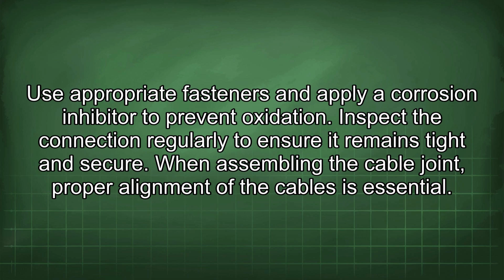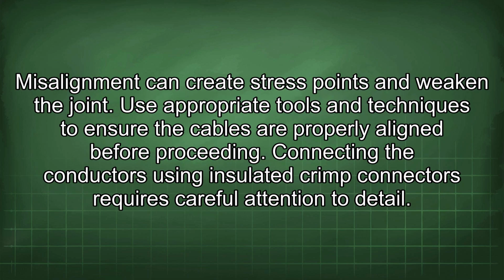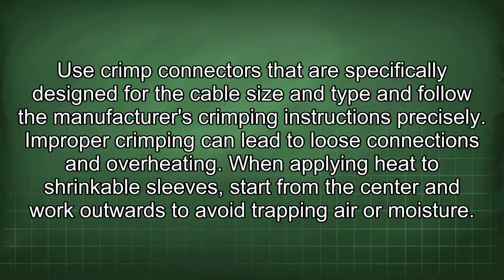When assembling the cable joint, proper alignment of the cables is essential. Misalignment can create stress points and weaken the joint. Use appropriate tools and techniques to ensure the cables are properly aligned before proceeding. Connecting the conductors using insulated crimp connectors requires careful attention to detail. Use crimp connectors that are specifically designed for the cable size and type and follow the manufacturer's crimping instructions precisely. Improper crimping can lead to loose connections and overheating.